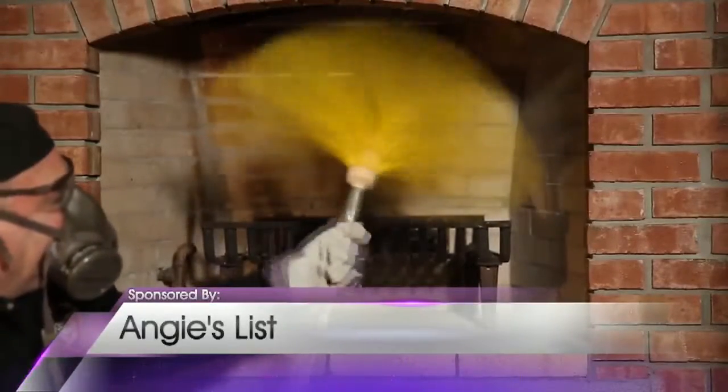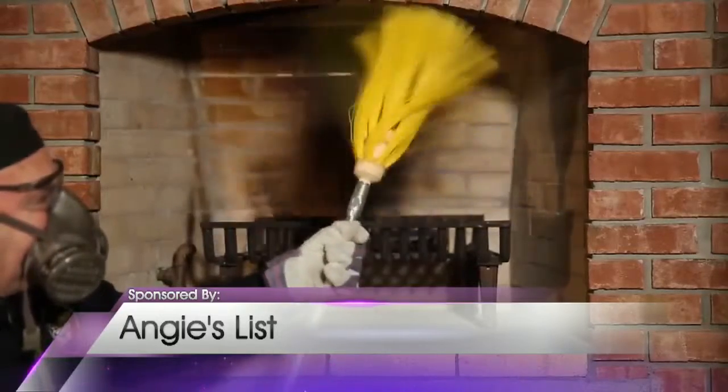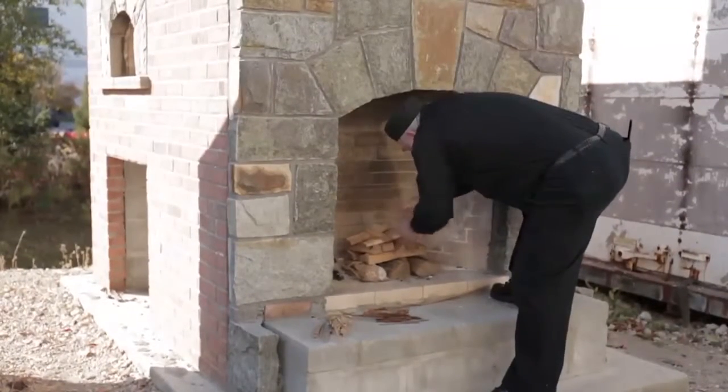Ashley Eldridge has been sweeping chimneys for decades, so poorly maintained fireplaces don't surprise him. I've seen dampers installed backwards. I've seen fireplaces that were incapable of functioning properly. Most of the fireplaces are not actually built the way that they should be built. The smoke chamber should be very smooth as it leads the smoke into the flue, and it's a rarity to find that done properly.